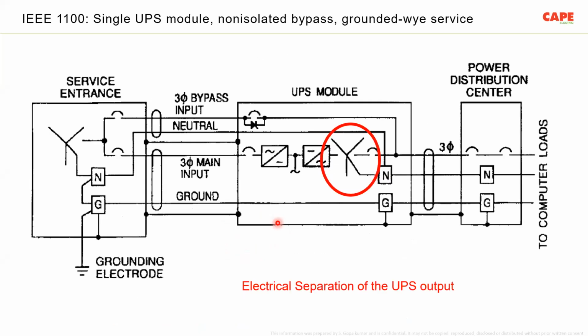So, UPS is always a very critical subject in our electricity usage, because we have a lot of power cuts and as a result we use a lot of UPS. Now, I took this picture again from IEEE 1100. IEEE 1100 is a recommended practice for grounding of electronic installations. There are 8 types of UPS installations explained in this standard. Now, this is a single module UPS, a non-isolated bypass and grounded Y connection. Don't look at the entire picture, it takes a few minutes to understand. Just look at what is shown in this red box or red ring.